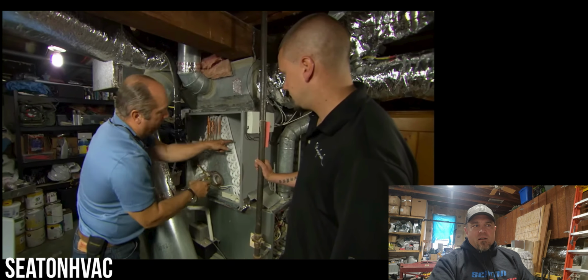And that's a good view of that plenum right there. See the supply plenum off the top of the coil? You know, if you're going to do a system like this in your basement and add AC to it, what they should have done is the whole system and replaced that furnace. They'd have gained themselves another 7 inches because the new furnace would be 33 inches tall, and the existing one looks like it's 40 inches.